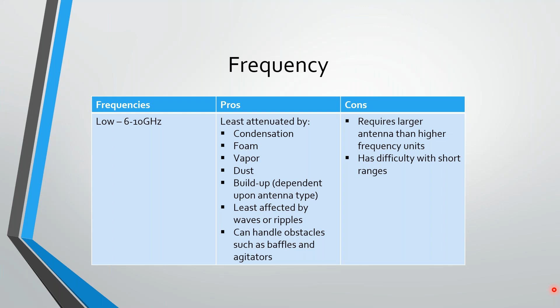Some of the cons: they do require larger antennas. So again, going back to that example I had before, where maybe the process connection is 4 inches, and we look at a low frequency device and it's going to require a 6-inch diameter antenna, we're not going to be able to use that device for this application. We're going to have to go to a different device. Low frequency devices, though, do have a problem with measuring short ranges. So if we have a very short range, we're going to have to go to a higher frequency device.